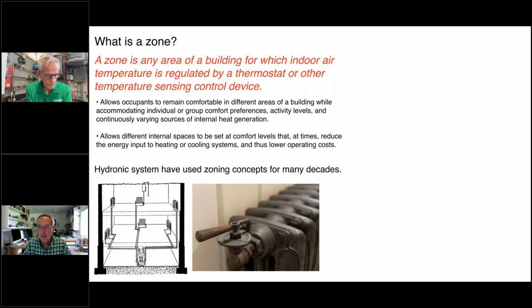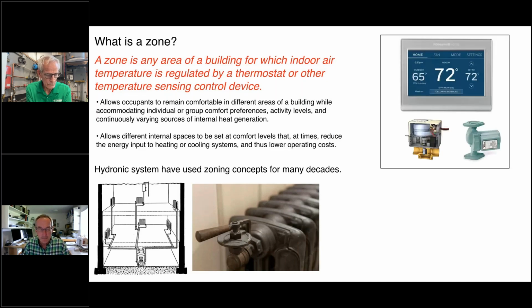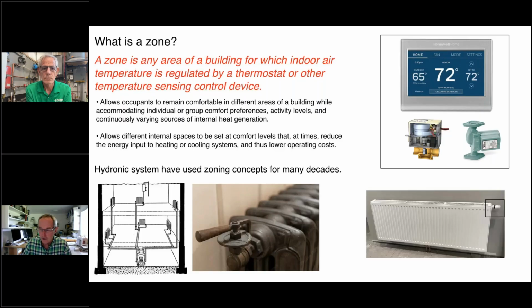And of course, today we've got modern thermostats, whether they're Wi-Fi based or just digital thermostats. And those are controlling devices such as zone valves here or zone circulators. And again, we're going to talk about both of those. But we're also going to talk about devices that don't require electricity. And I drew a little box around that. This is a thermostatic radiator valve, and that's attached to a panel radiator. And that allows that radiator to adjust to changes in air temperature.